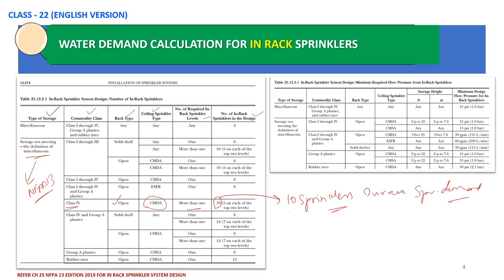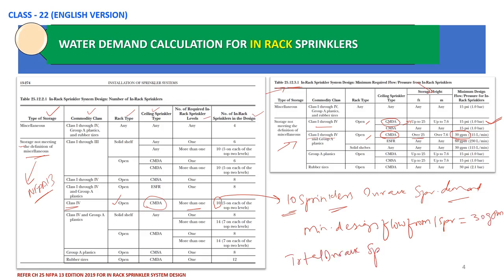From that table we determined how many sprinklers to consider. From Table 25.12.3.1 we can calculate the minimum design flow for one in-rack sprinkler. For Class 1 through Class 4 with storage height more than 25 feet, we consider a flow of 30 GPM per sprinkler. So the total in-rack sprinkler demand will be 10 multiplied by 30, giving 300 GPM.